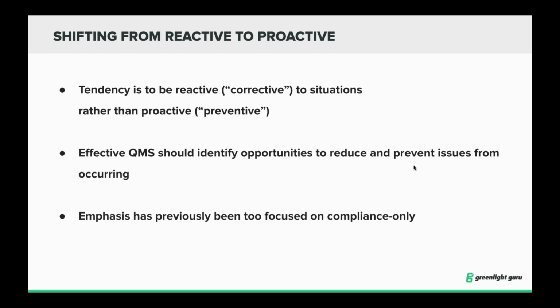And I mentioned I am a design control nerd. From a product design perspective, to me, that's the best opportunity. When I'm going through the design and development process, I want to be as holistic and comprehensive as possible, not just focus on the design and development of the particular device that I'm interested in producing, but look at what else is out there. Are there other products that are similar, competitive products, et cetera, that may have had some issues with a particular feature or material or functionality or what have you? I should be going to those sources of information to understand what challenges others who brought products to market before me were facing.